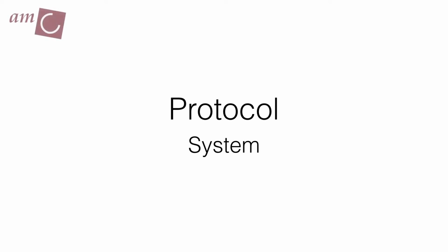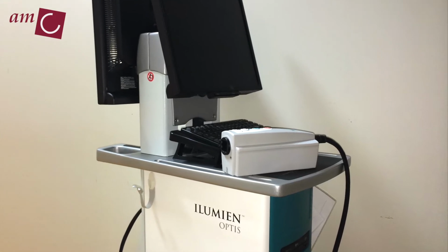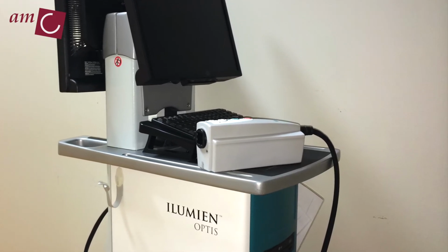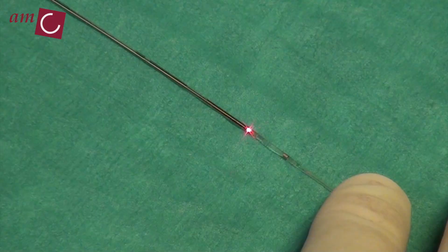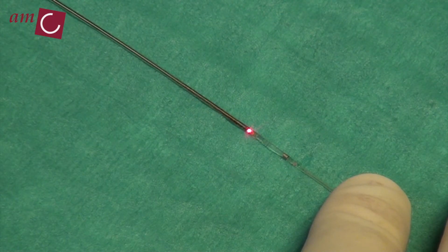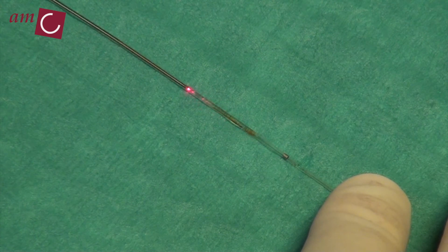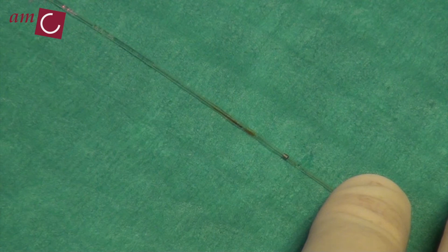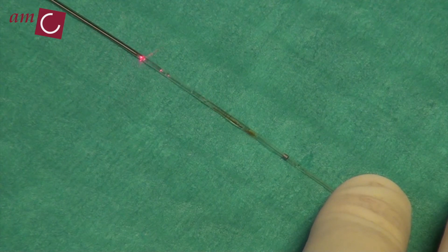In this demonstration, we use the commercially available Ilumien Optis OCT system connected to a Dragonfly Duo intravascular imaging probe. The Dragonfly Duo is a rotational probe scanning at a 90-degree angle. It has an outer diameter of 2.7 French, 0.9 millimeters, and an insertable length of 135 centimeters.